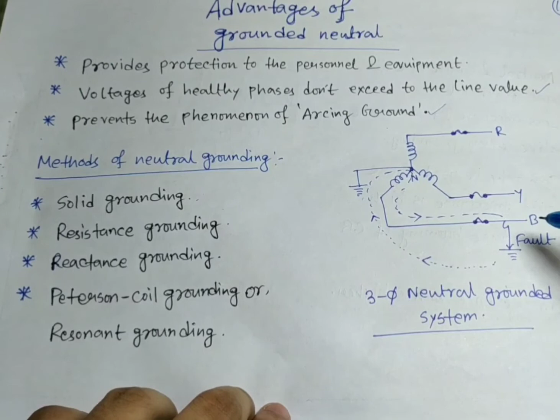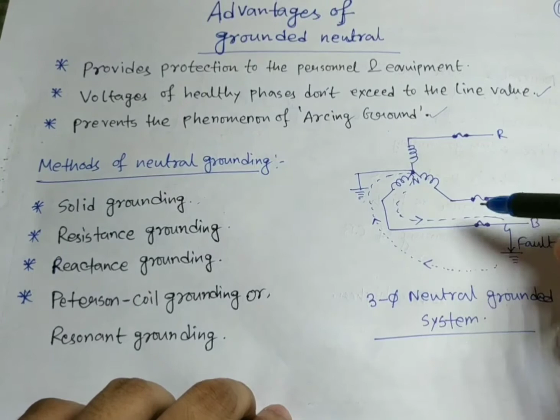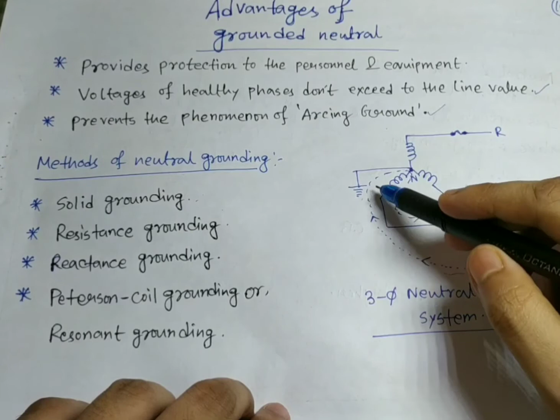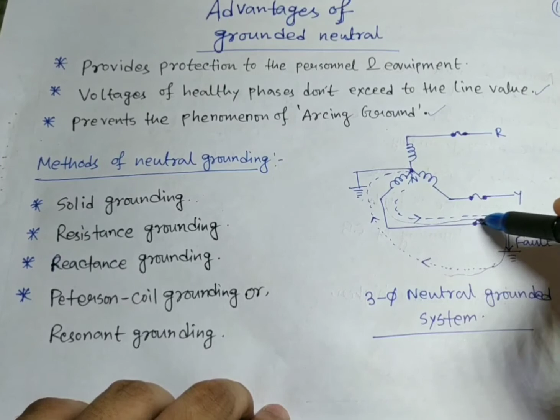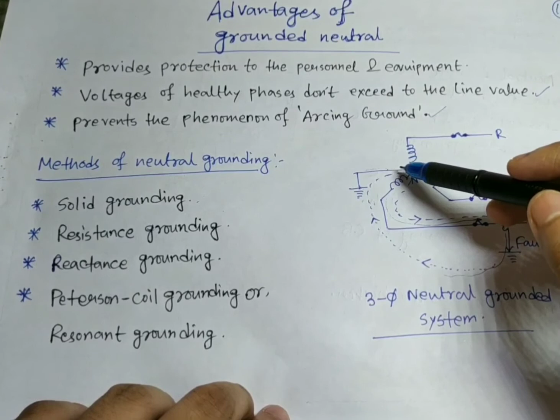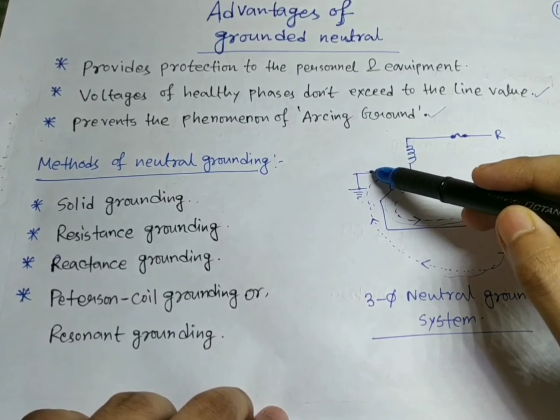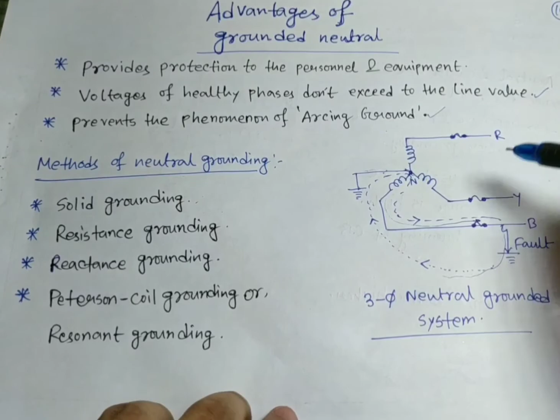Before going further, this is your 3-phase neutral grounded system, and suppose in this phase a fault is happening. In that case, obviously the fault current will directly flow via ground, come back to its neutral point, and again come back to its faulty phase using this neutral wire. Here I have shown solid grounding, but it can be of many types. It can also be resistance grounding, where one resistance is connected here, or reactance grounding, or resonant grounding. We'll see one by one.